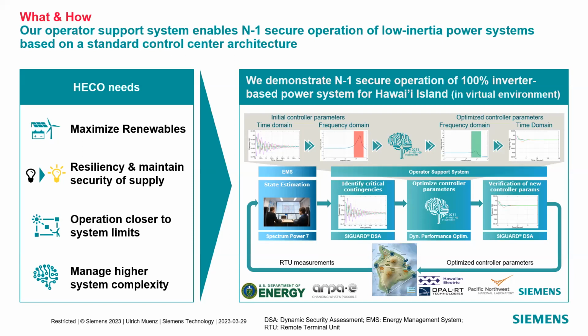This is similar to what Jin showed: we take the oscillations into the frequency domain, where peaks correspond to oscillations in the system. We developed an algorithm that suppresses these peaks by tuning different controller parameters—Jing mentioned droop gains; for conventional power plants it could be power system stabilizer parameters. It could be practically any tunable parameter on any generation asset.